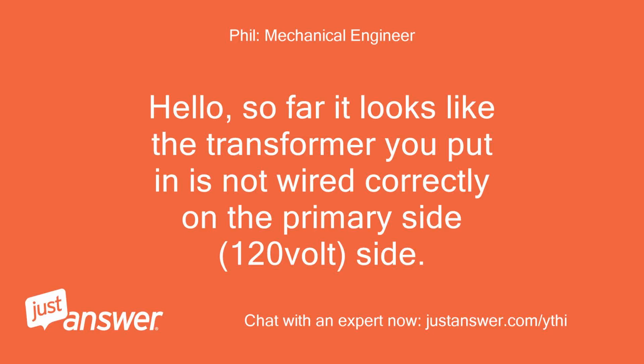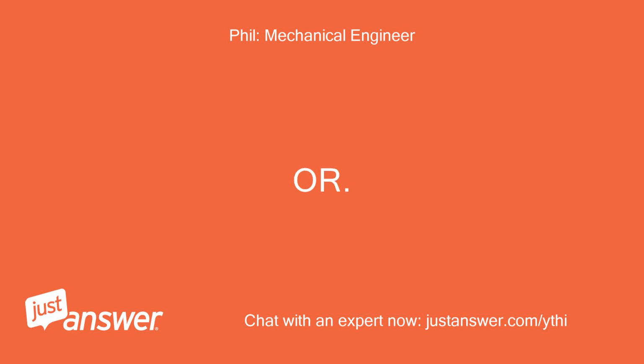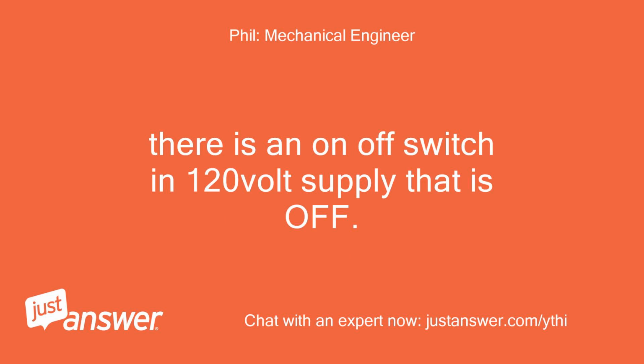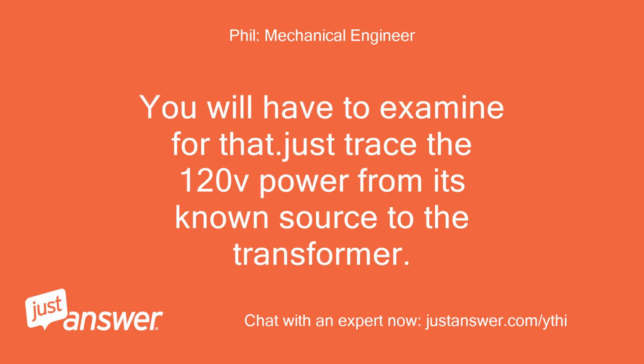Hello. So far it looks like the transformer you put in is not wired correctly on the primary side, 120 volt side. Or there is an on-off switch in the 120 volt supply that is off. You will have to examine for that. Just trace the 120V power from its known source to the transformer.